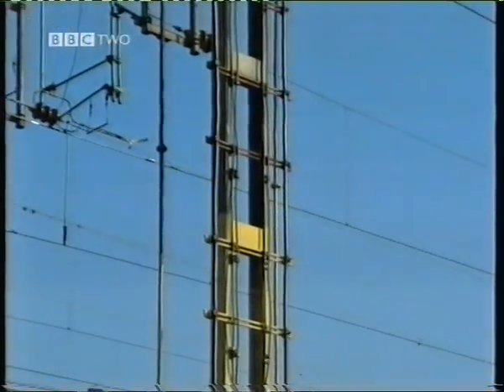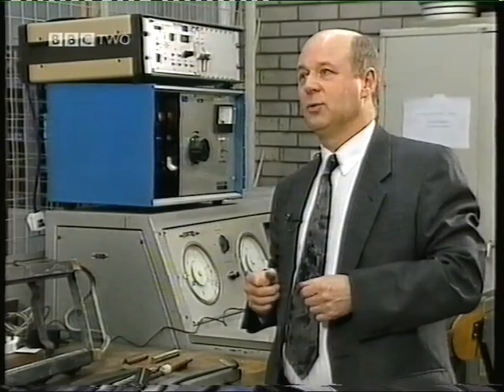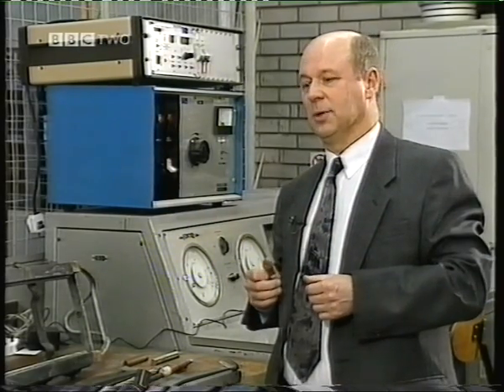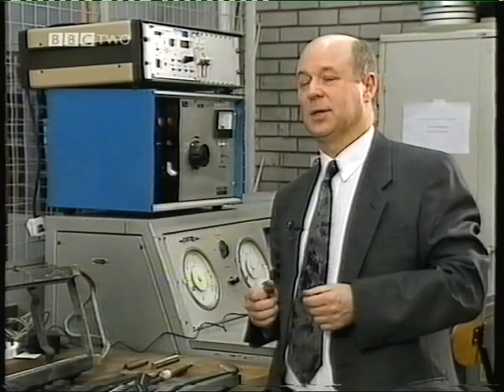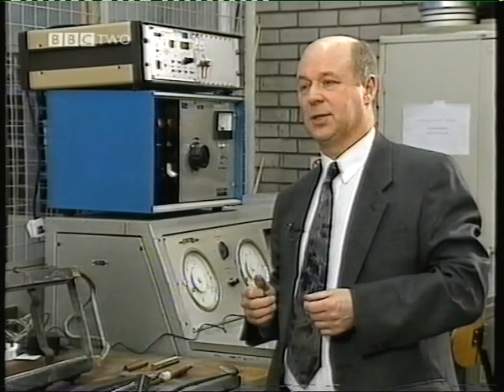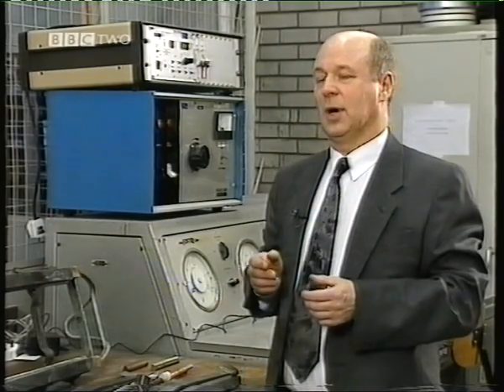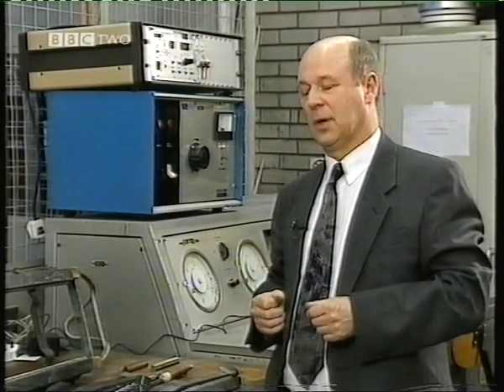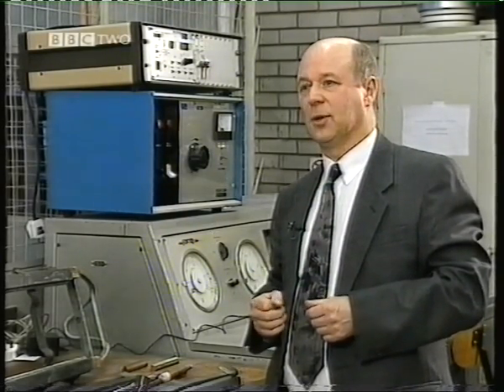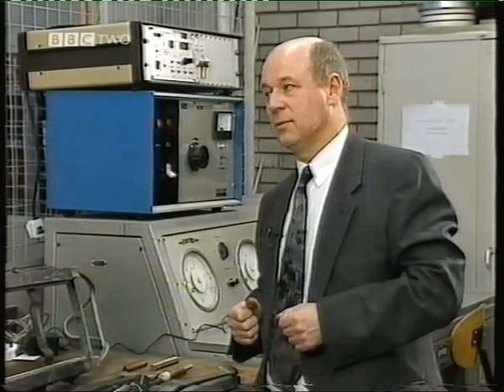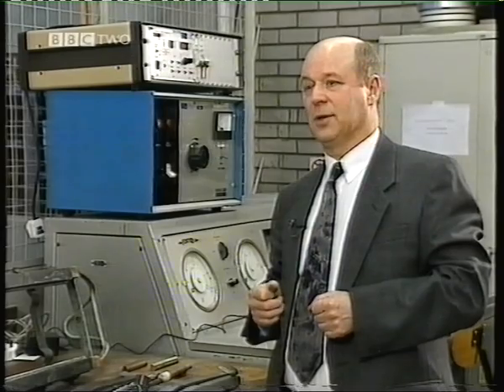The wire is not continuous, it's broken into sections for tensioning and for electrical sections. Every 2 kilometres the wire has a series of weights providing about 1 ton tension. The wire expands between normal low temperature minus 20 degrees C and the highest temperature about 60 degrees C. It expands about 2 metres, and the wire has to be sectioned about every 2 kilometres to allow for that expansion. Electrically, the overhead wire is broken into sections about 15 kilometres long, where power is fed in from the electricity board in through our feeder stations.